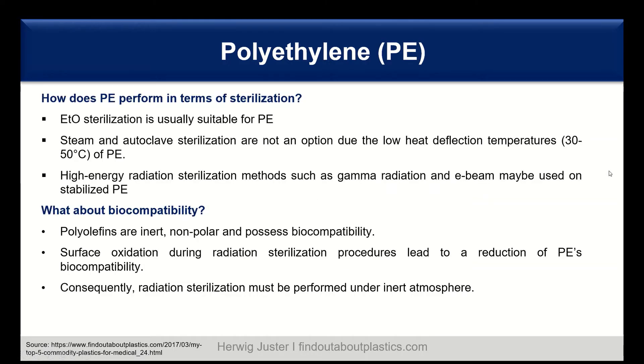How does polyethylene perform in terms of sterilization? Ethylene oxide sterilization, short EtO sterilization, is usually suitable for polyethylene. Steam and autoclave sterilization are not an option because polyethylene has a low heat deflection temperature, and the temperature impact causes deformation of the part.